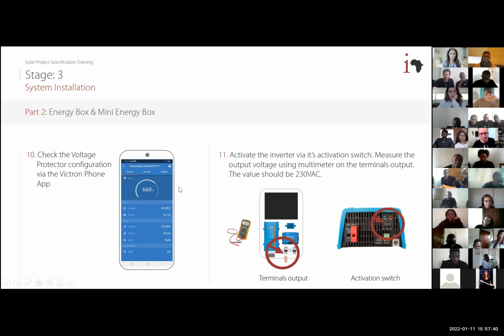The next step is the voltage protector, as I mentioned. It also has the Victron phone application - you pick it from the list when you open the app, and you can check that it is well configured. Checking voltage protector operation directly is a bit hard, since you'd need to let the battery drain until the minimum limit. So basically, what you do is check with the Victron phone application on site that the configuration of the voltage protector is accurate. This is the voltage protector.